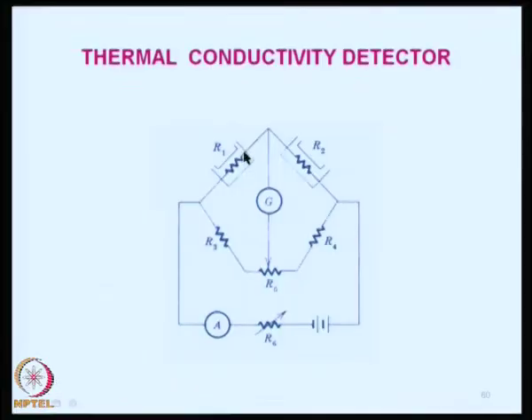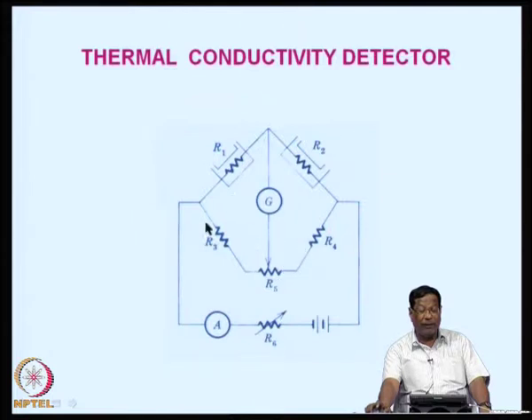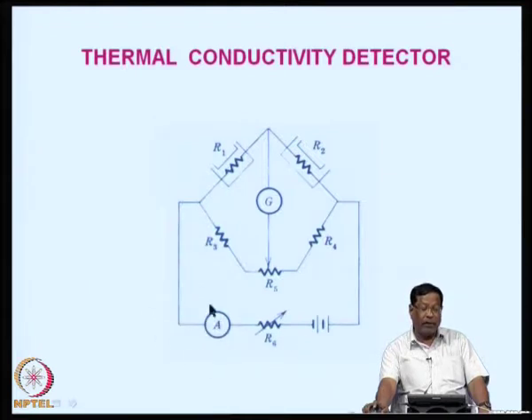The cell cavity in which the sample enters is approximately 2.5 ml for large thermal conductivity detectors, or 0.025 ml for micro TCD. The total volume could be maximum 5 ml for the whole TCD. The system is very simple, consisting of different resistance wires, a galvanometer, a resistor, an ammeter, and a power supply.